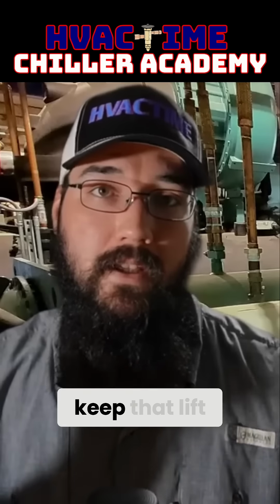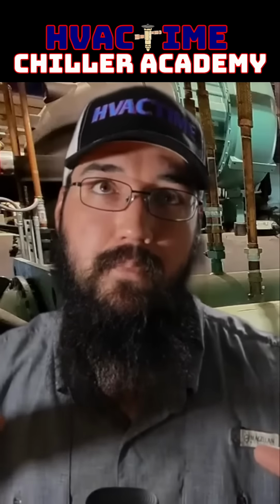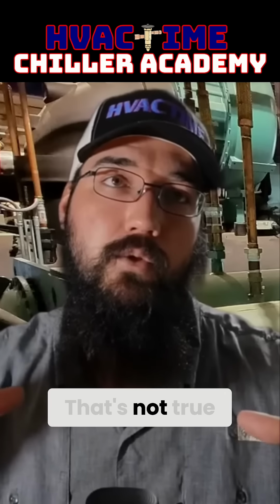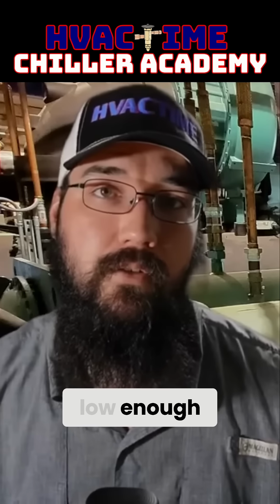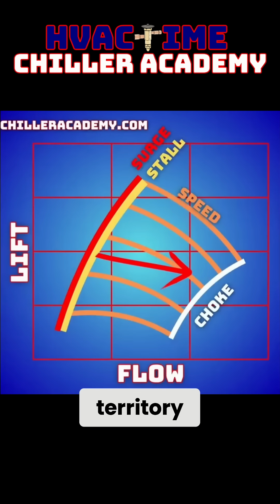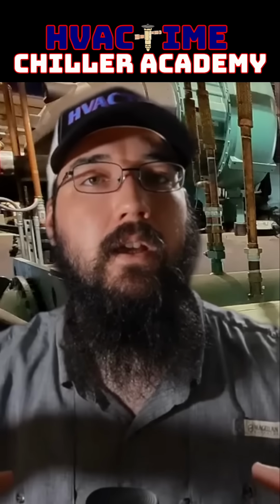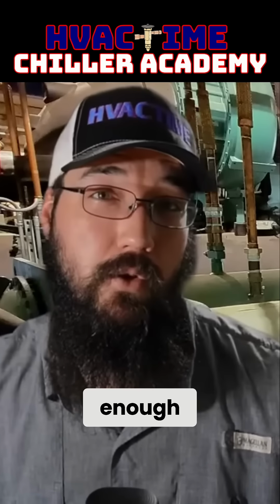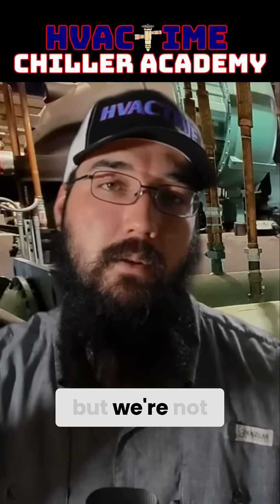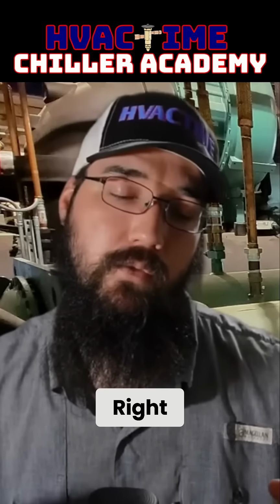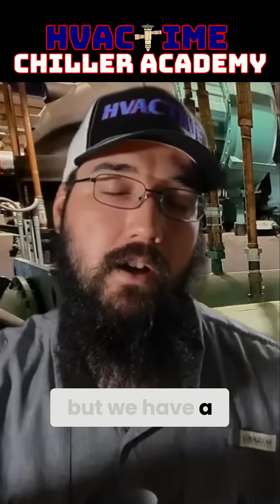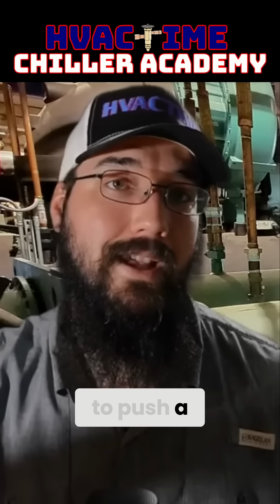Now, we want to keep that lift value as not as low as we can. That's not true, but low enough, okay? Because if we go too low, that's where we get into the choke territory. Sometimes that could mean we don't have enough load on the evaporator, but we're not able to cool the condenser down, right? So if we have a low evap load, but we have a hot condenser, that's going to push a really high lift.